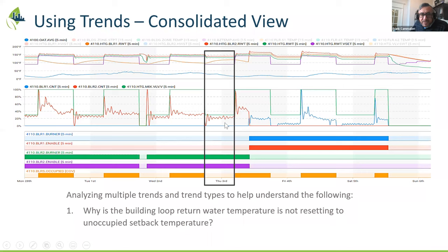So basically, having this valve position set at 30% is allowing too much water to go into the building loop. 30% of the water goes into the primary loop, and that minimum of water that has to stay at high, hot temperatures goes into the building loop, and that minimum is just set way too high for this to reset.